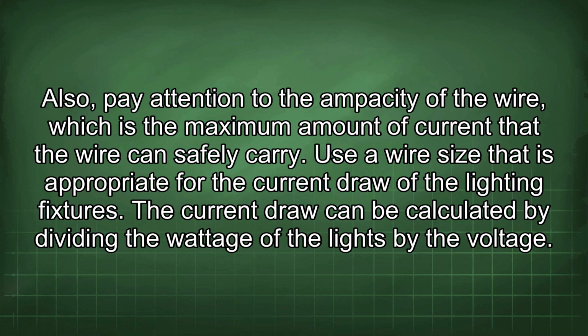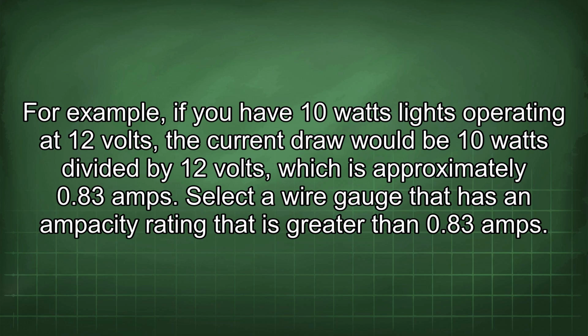The current draw can be calculated by dividing the wattage of the lights by the voltage. For example, if you have 10 watt lights operating at 12 volts, the current draw would be 10 watts divided by 12 volts, which is approximately 0.83 amps. Select a wire gauge that has an ampacity rating that is greater than 0.83 amps.